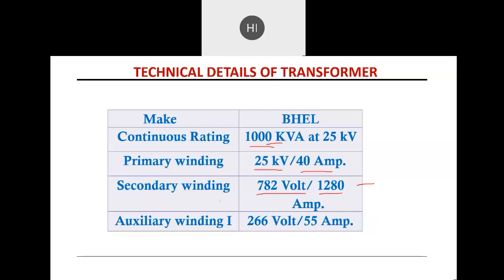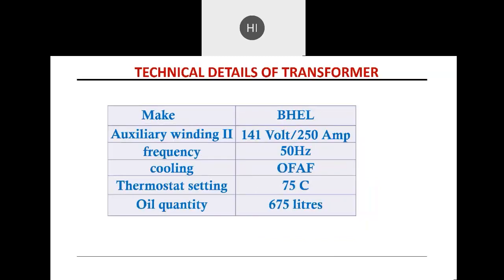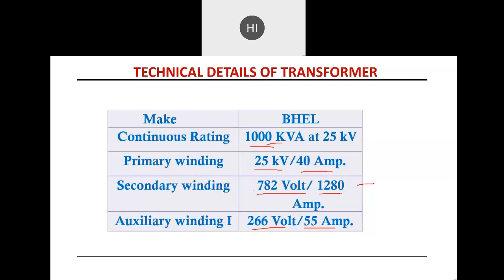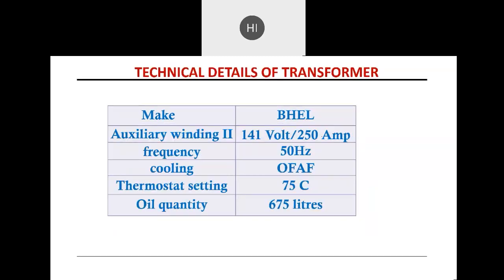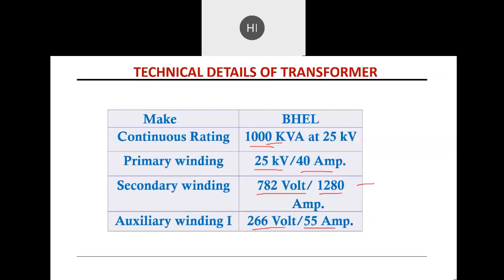We also have two other auxiliary windings. The first auxiliary winding gives 266 volts at 55 amperes, and the second auxiliary winding gives 141 volts at 250 amperes. As an exercise, if you multiply 782 by 1280, 266 by 55, and 141 by 250, this will be equal to 25 multiplied by 40.